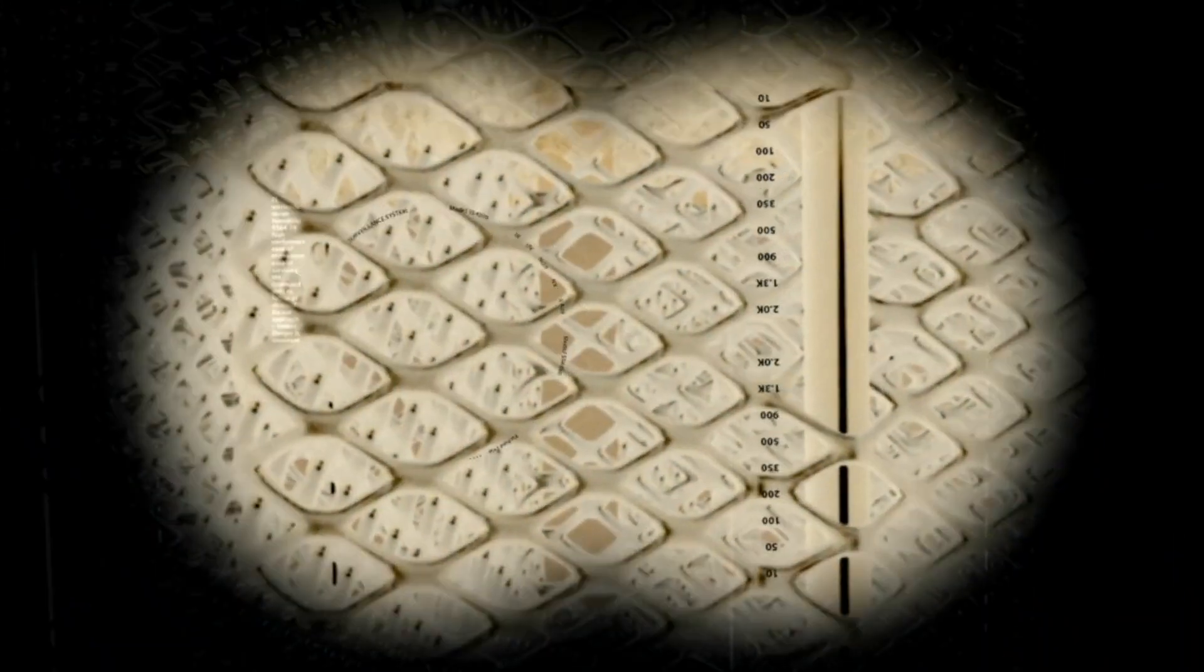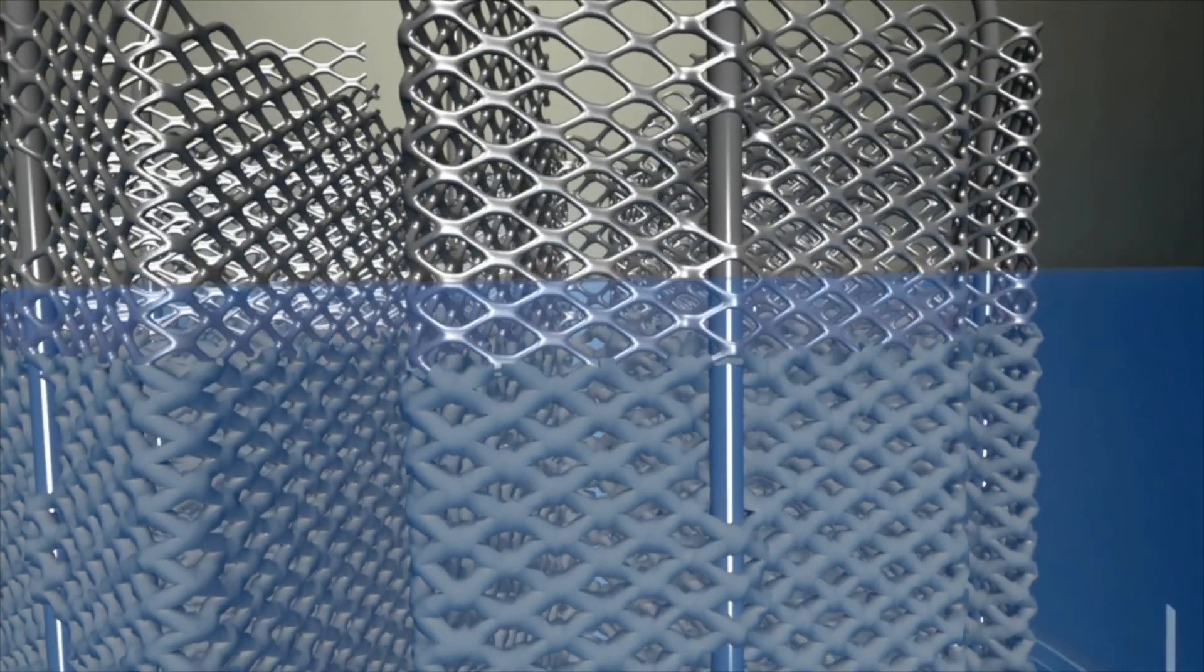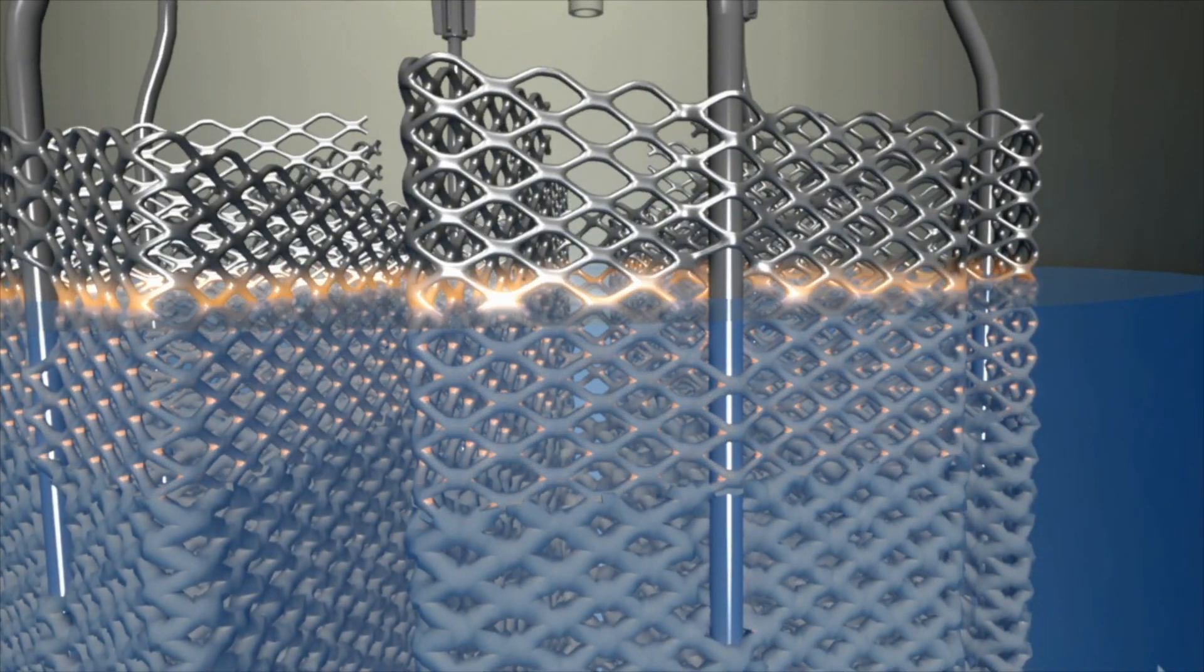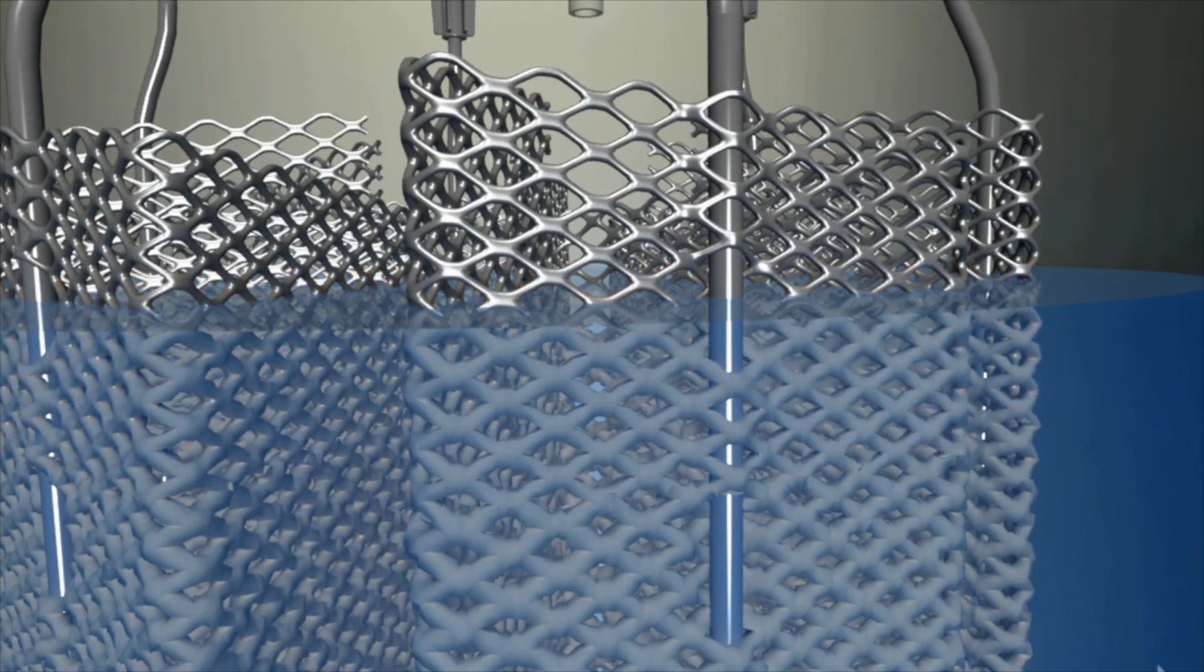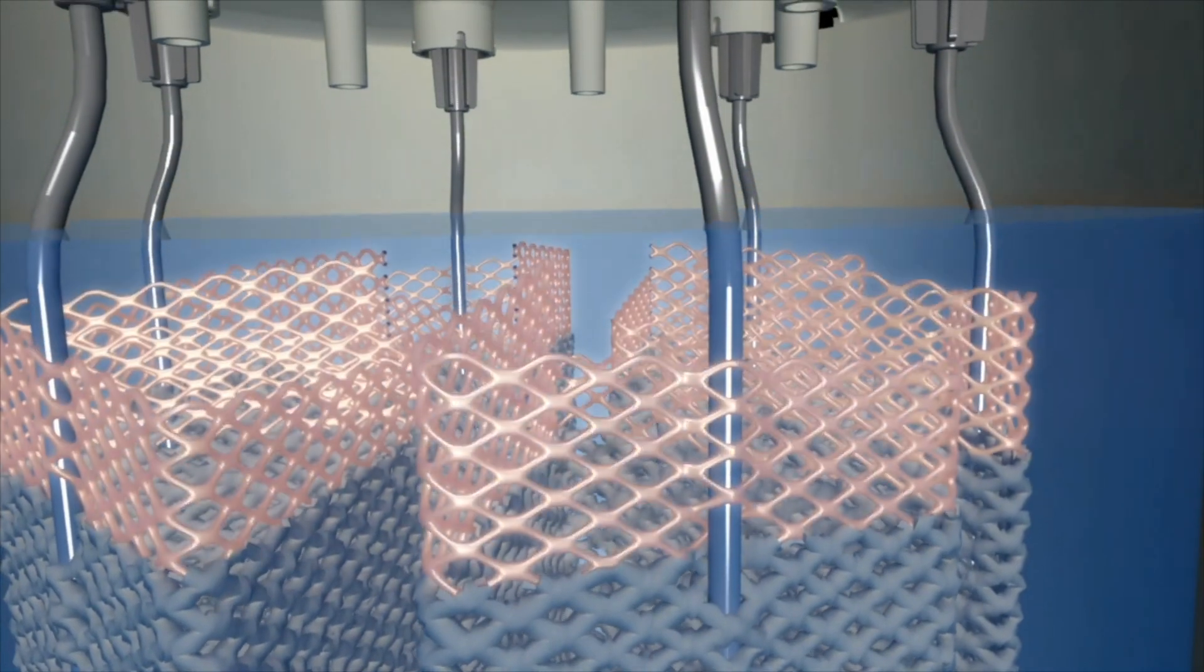Continuous operation results in mineral deposits building up on the electrodes as well. The control system detects this and automatically raises the water level. Clean electrode surfaces are then submerged, maintaining optimal performance and accurate humidity control.